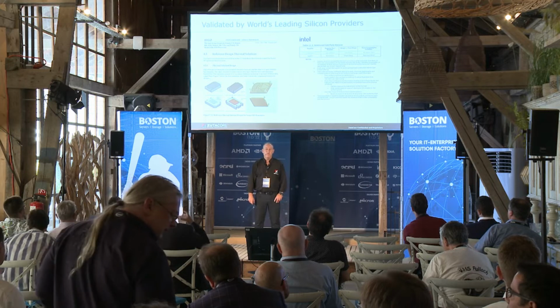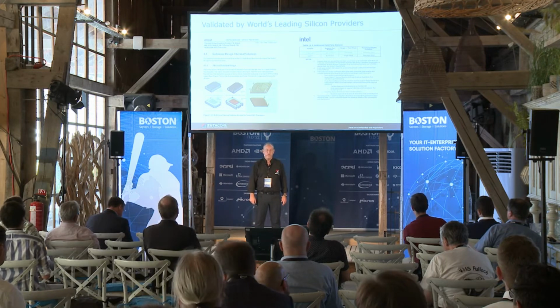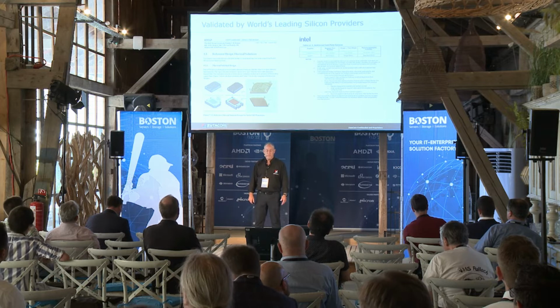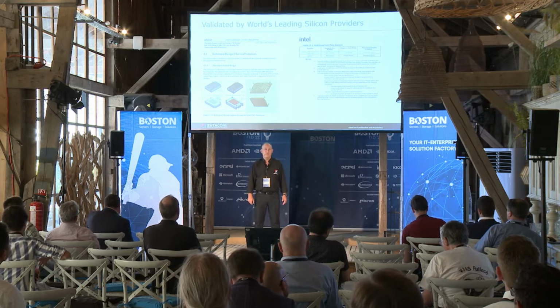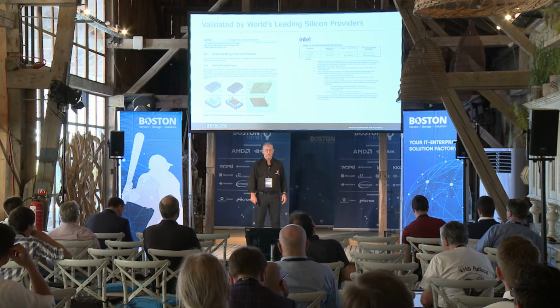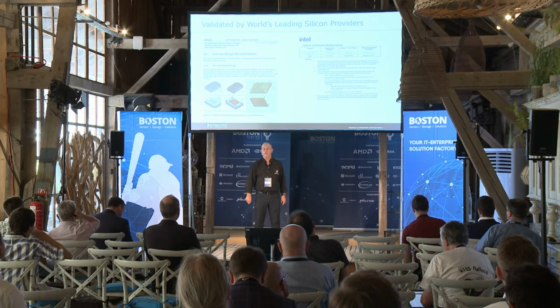Now, ZutaCore has been working with the silicon manufacturers, and today when you design a server, if you're a server manufacturer, you can find it in a thermal design guide from AMD or from Intel. This is, for example, Intel, the Sapphire Rapids, the new generation coming out next year. You already have in the thermal design guide their guidance that if you want to use two-phase, ZutaCore is their solution. And this was a hard place to get to. It looks like a line on a paper, but it was hard. It was about 1.5 years of testing in Intel labs until they got this into it, and working with AMD very closely on their chips into releases.